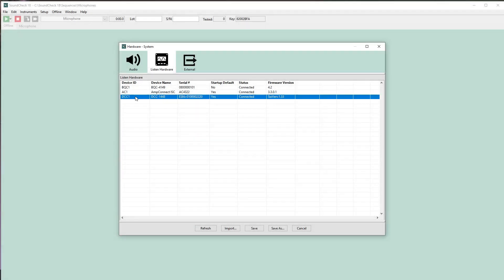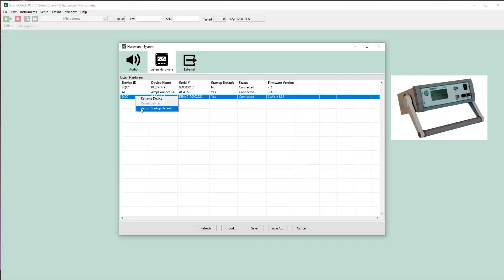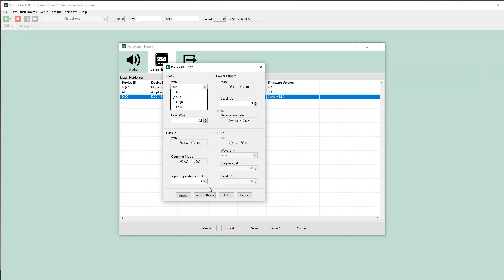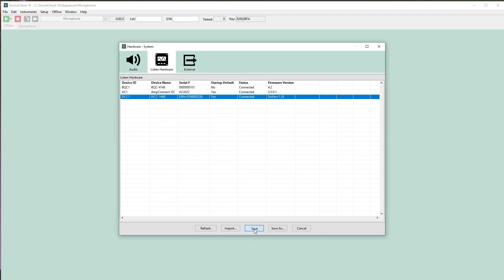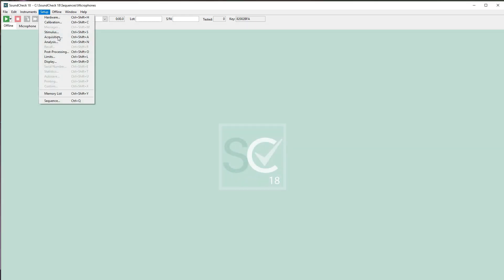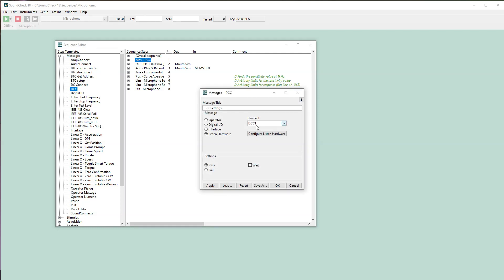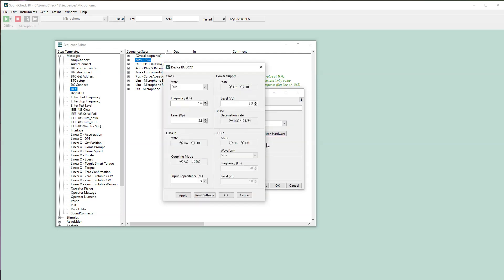The PDM MEMS microphone interfaces can now be fully controlled from within Soundcheck. This offers faster setup of the measurement interfaces with Soundcheck as well as greater measurement reliability, as the device settings can be built into the test sequence. Sequences using the R&D-grade DCC1448 interface will also work seamlessly with the production-grade PQC1448, making it much simpler to transition sequences from the R&D lab to the production line.